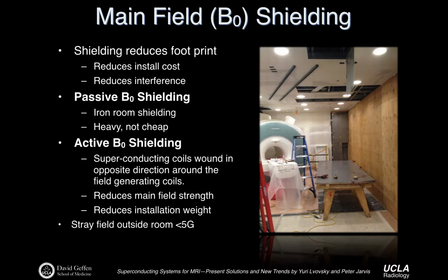A couple things to keep in mind. I've mentioned this already, but the main field requires some shielding. This is a system that was being installed here several years ago, and what you'll see is that these here are just sheets of steel, just low-carbon steel. These sheets are being placed up against the wall, so you can see panels of steel against the wall here, against the floor, and so forth.